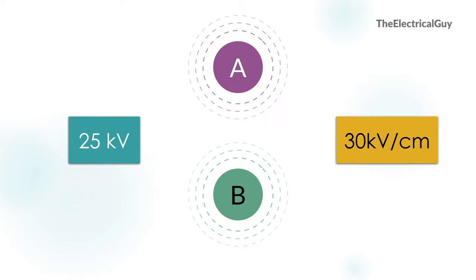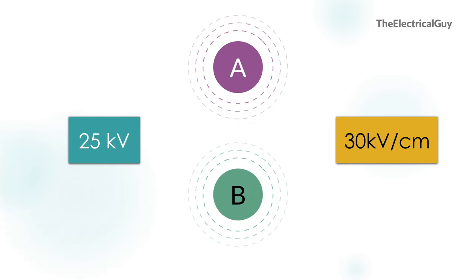This current is almost negligible if the electric field intensity is less than 30kV per centimeter. This 30kV per centimeter value is based on studies and calculations — it depends upon many other factors which we will see in this video. If the electric field intensity is less than 30kV per centimeter, the current flowing between the two electrodes is negligible and you can ignore it.